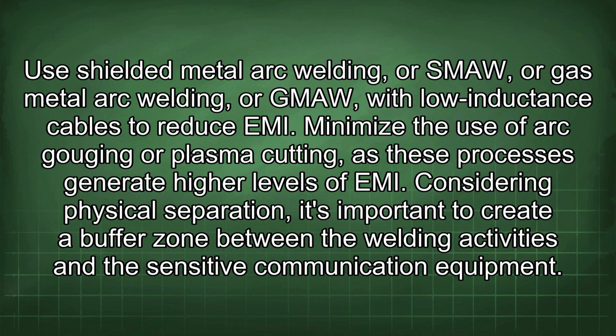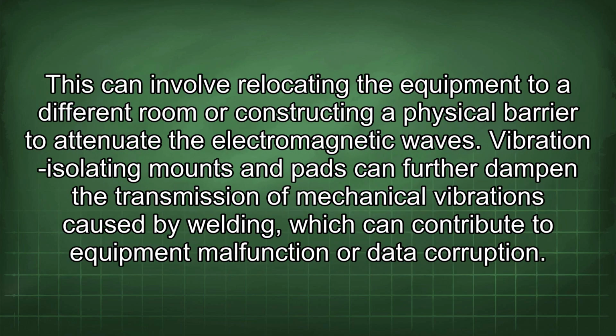Considering physical separation, it's important to create a buffer zone between the welding activities and the sensitive communication equipment. This can involve relocating the equipment to a different room or constructing a physical barrier to attenuate the electromagnetic waves. Vibration isolating mounts and pads can further dampen the transmission of mechanical vibrations caused by welding, which can contribute to equipment malfunction or data corruption.